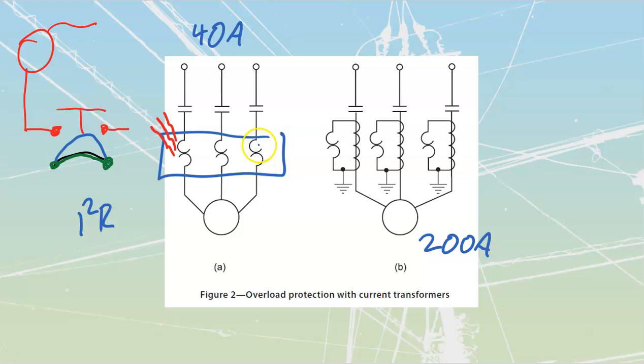the overload heaters. So the overload heaters inside of here, they're fine for 40, but 200 amp overload heaters would be ridiculous. First of all, they're going to be incredibly hot. And secondly, they're going to be incredibly bulky and expensive. So what we'll do is we will use a CT that will then take our 200 amps down to a 5 amp. So let's use a 200 to 5. That means that inside of the secondary circuit that we see, this over here, we've got no more than 5 amps that's going to be getting driven through there. If I get up to 200 amps. If I would be running at less than 200 amps, I'm going to have less than 5 amps. If I go over top of 200 amps, I'm going to go over top of 5 amps. So all I would need to do is have an overload heater inside of here.